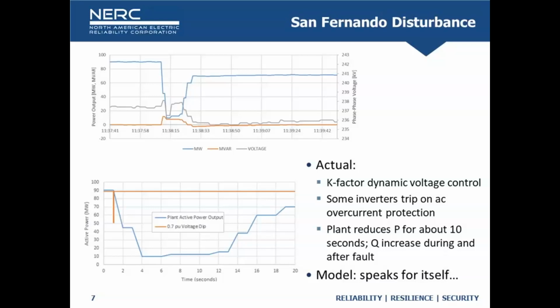That difference is the tripping of inverters on the AC overcurrent protection. But what happens is the plant reduces its active power output down to about 10 megawatts, takes 10, 15 seconds, and it sits down at 10 megawatts and then slowly recovers back to some output level.